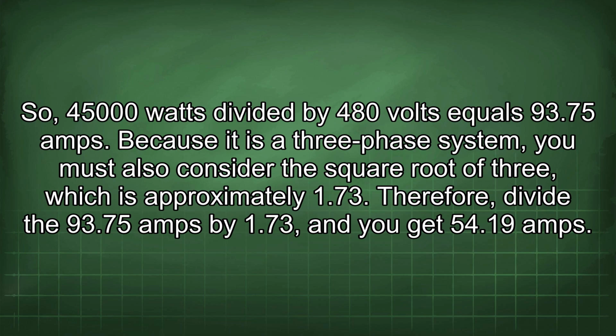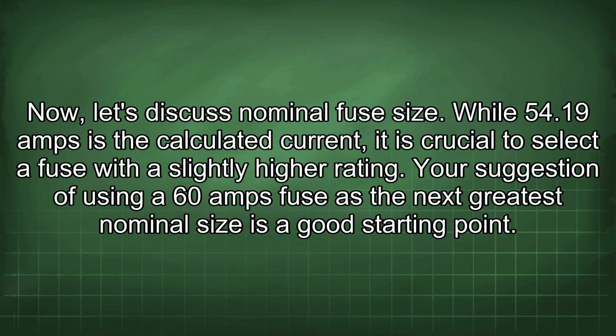Because it is a three-phase system, you must also consider the square root of 3, which is approximately 1.73. Therefore, divide the 93.75 amps by 1.73, and you get 54.19 amps. Now let's discuss nominal fuse size. While 54.19 amps is the calculated current, it is crucial to select a fuse with a slightly higher rating. Your suggestion of using a 60 amp fuse as the next greatest nominal size is a good starting point.